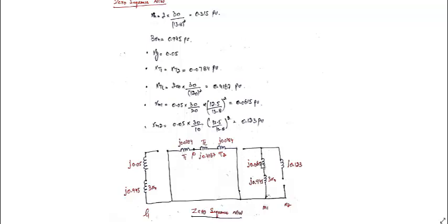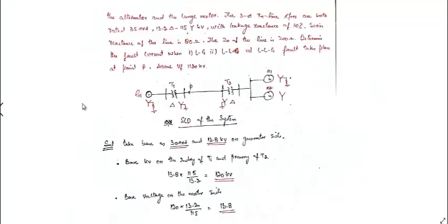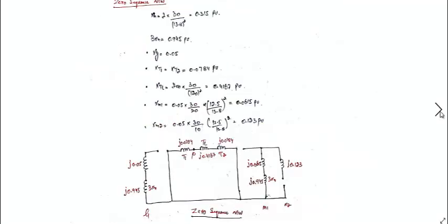So here, this is the generator, sorry, motor M1, because motor M1 contains X 3 times Xn and its own 0.0615. And motor M2, since you can see the neutral of M2 is not connected to ground, it is shown open circuited. This is the zero sequence network of the given power system.